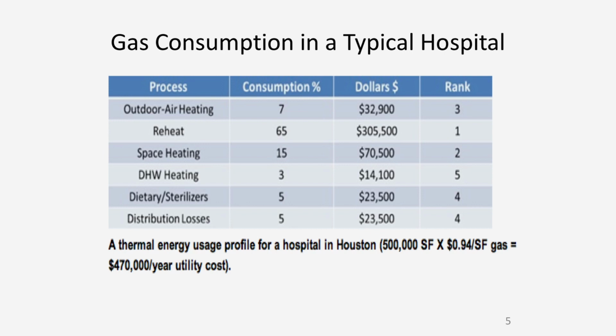Now, what you ask, you're thinking to yourself, what does reheat mean? Well, in the ventilation industry, generally speaking we deliver air, roughly for those of you who are Fahrenheit minded, 55 degrees Fahrenheit, and we heat it up to whatever temperature we want on the local reheats. That's expensive. We're going to talk about ways where we can reduce that cost and really apply it in a good infection prevention method for enhancing the safety, internal safety of the hospital.